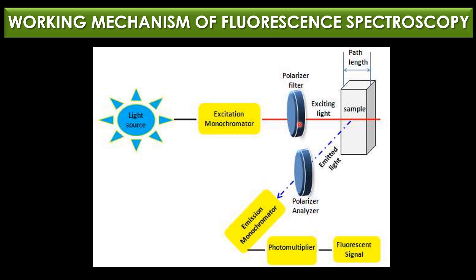A polarized filter is used to polarize the exciting light before it hits the sample. Polarization ensures that the light waves vibrate in a specific direction, which is useful for fluorescence anisotropy experiments where the orientation of molecules is important. The sample — the material being studied — is then excited by this light, causing it to emit light at a different wavelength.